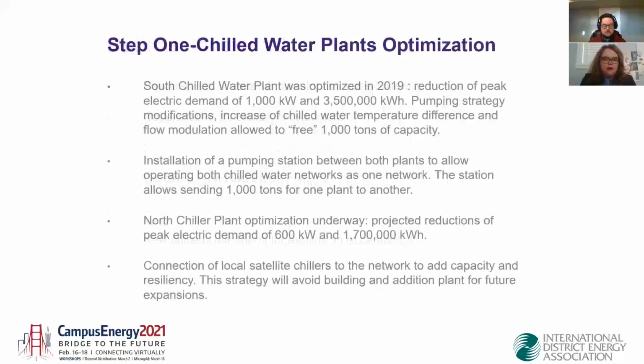So the beauty of this campus is that all buildings are connected together by the chilled water network, and that network is offline in winter. But when we look at it, it's a great network to transfer energy between one building and the other. So we're going to explain that a bit later on in the presentation. But before using that network, we had to optimize it. So first of all, the chilled water plants were optimized to reduce their peak electricity demand.